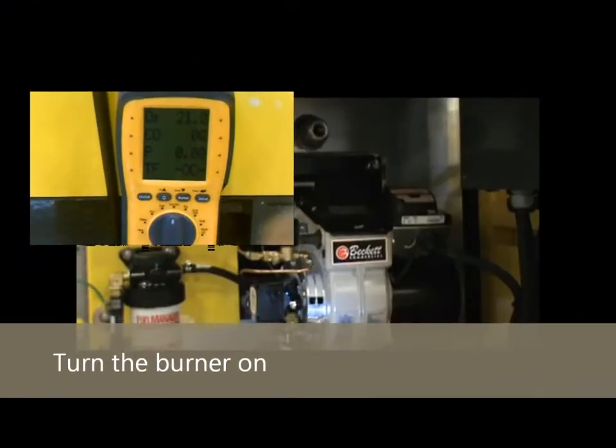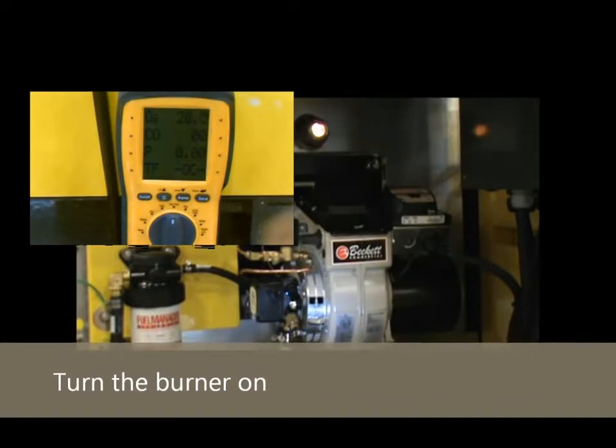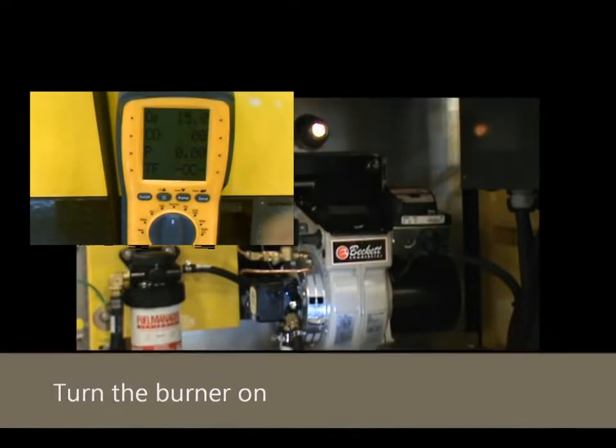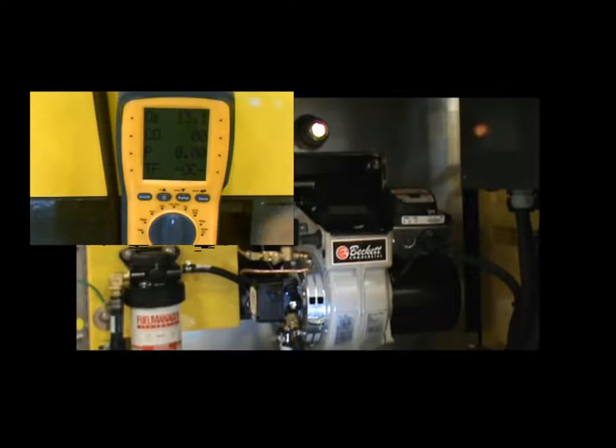When the burner starts, the oxygen level drops from 21%, or atmospheric level, to an unknown number. This number is the percentage of extra oxygen in the exhaust gas. This is the oxygen that has not been consumed in the combustion process. Wait for your O2 levels to stabilize before making any adjustments.